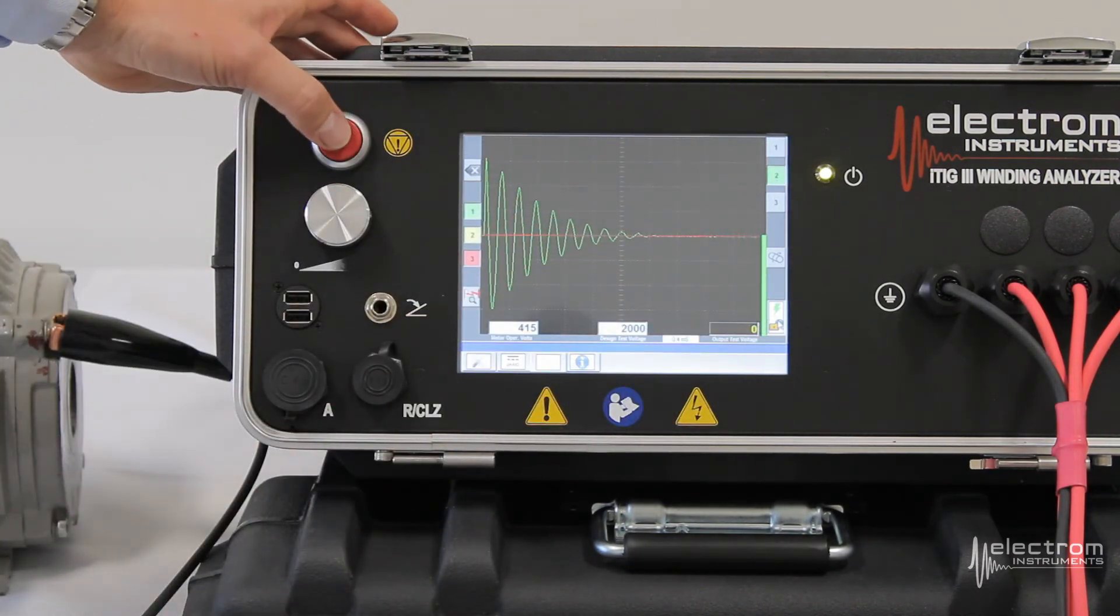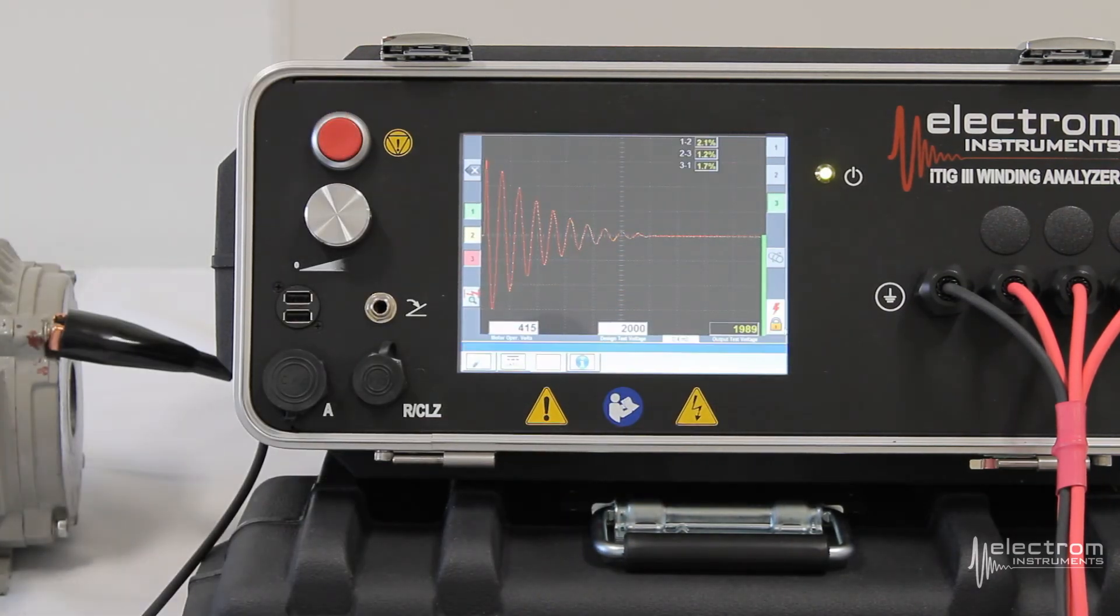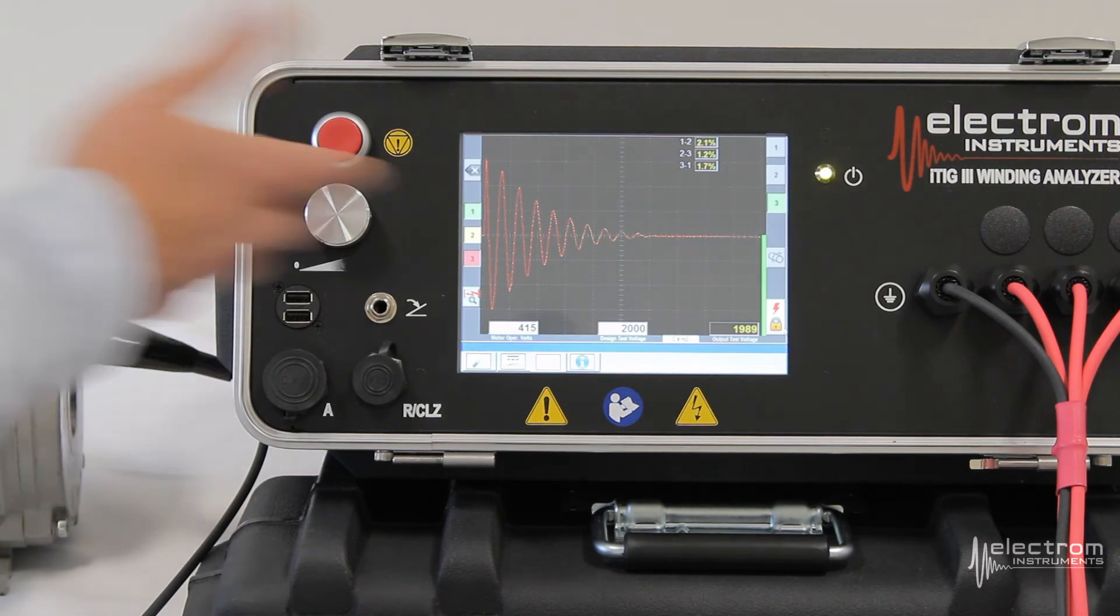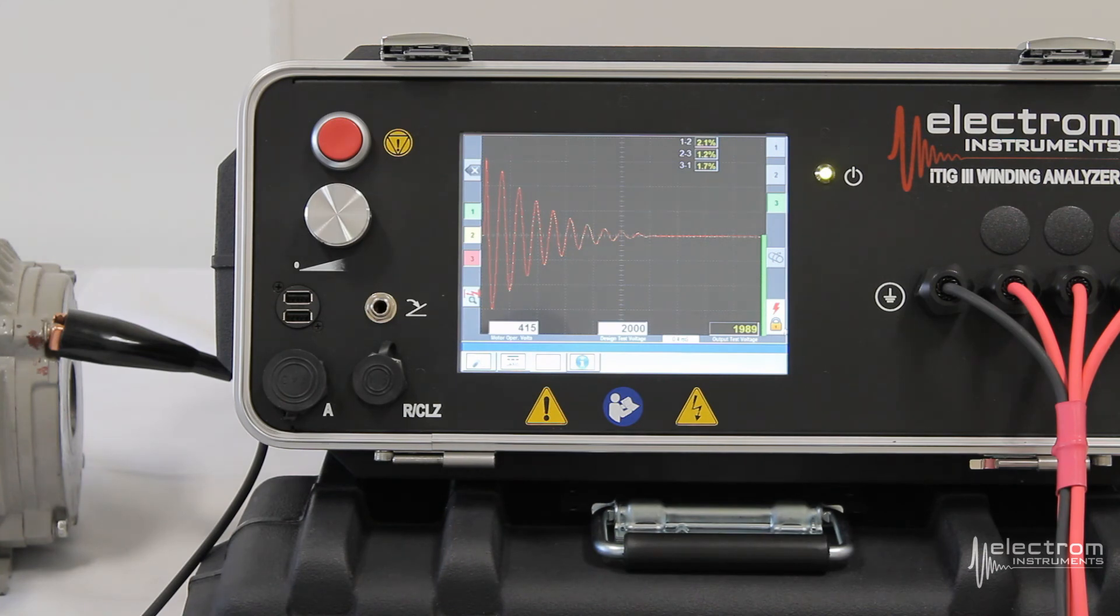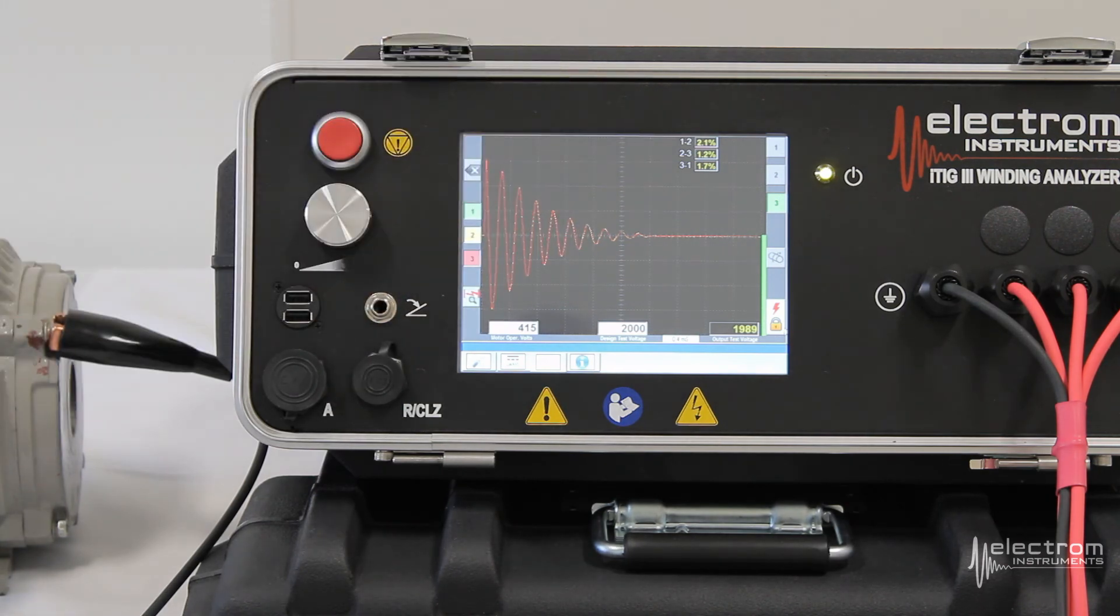Arm the instrument. Press the button. Phase 3, arm the instrument, press the button. And you now have your three surge waveforms for the three phases. As you can tell these are almost identical. So they're overlapping. It's hard to tell that we have three traces on the screen. But you get the percent wave differences listed on the top here.